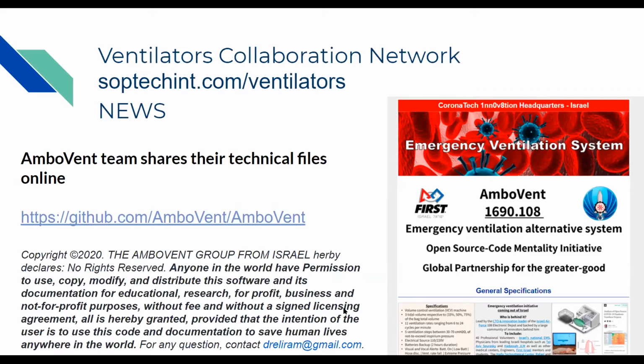No, and that's fine. For remote monitoring, that's probably fine. And I apologize, I don't know your expertise, but just on a side note, the sensors you have to use for the pressures for the human lung and the device, the signals are extremely low.